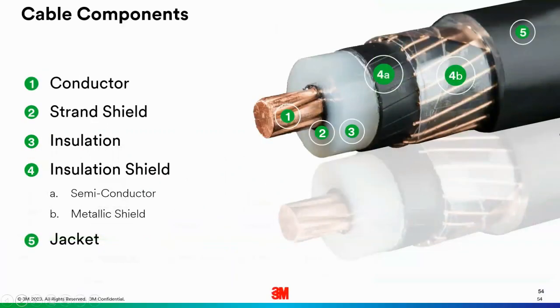So just some real basic construction of the cable, starting with basically 6 layers here. Starting with number 1, you have your conductor for carrying the current. And when choosing accessories, medium voltage cable accessories, like I'm going to be showing here in just a moment, it's very important to know the conductor size. So, are you working with a number 2 or a 2-aught or a 4-aught or a 750 kcmil? So the size of the conductor is very important.